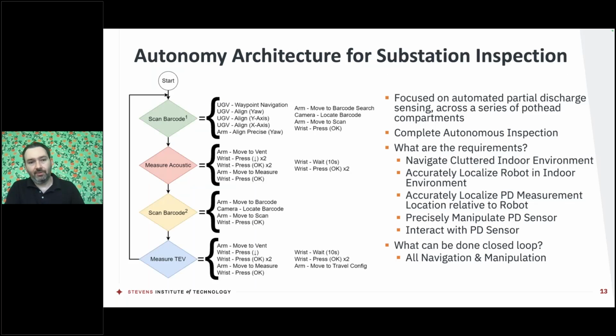Moving toward an autonomous substation inspection, we had to develop our own autonomy architecture. As George was discussing, two of the key measurements for PD inspection are TEV, the transient earth voltage measurement, where we were working with a handheld sensor that had to make physical contact with the outer panel of a pothead compartment, and an acoustic sample, which we had to take from the air vents of the panel of the pothead compartment. Then we also had to visually identify the exact compartment we were inspecting, which required us to visually detect a barcode placed on each of those compartments.